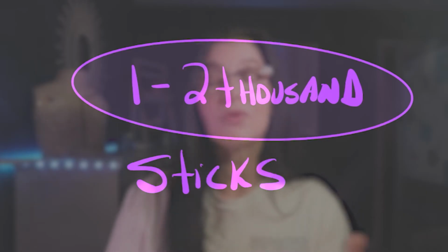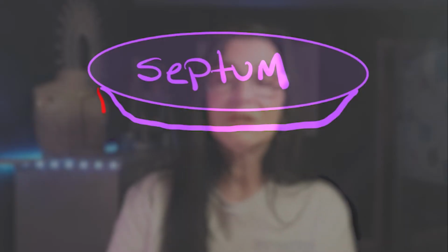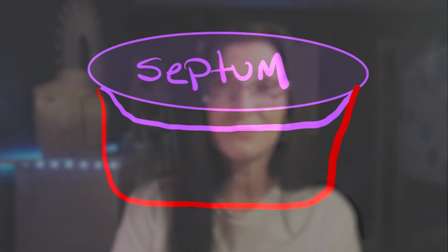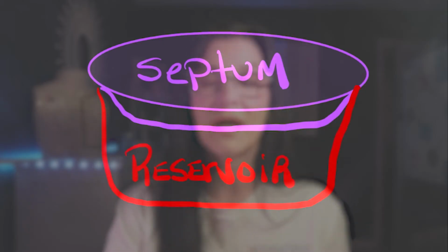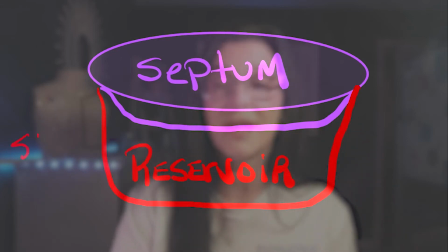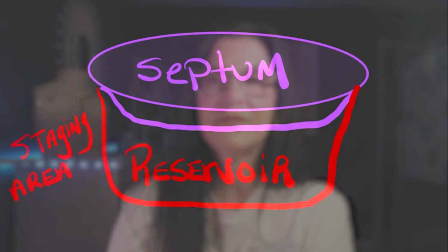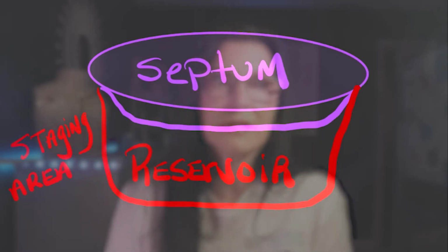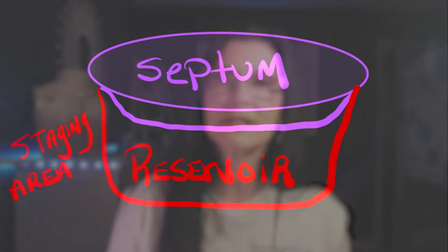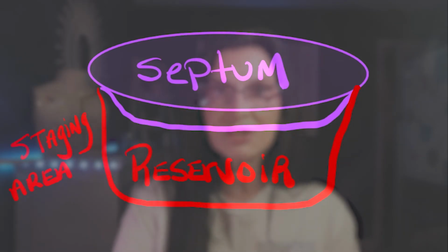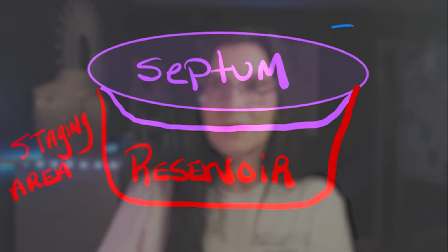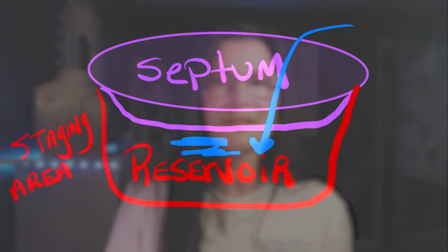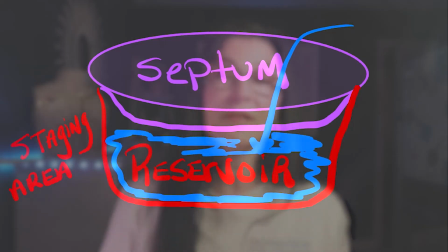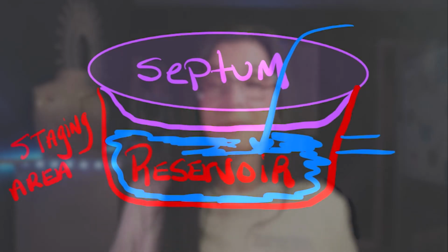On average, a silicone septum is designed to withstand anywhere from 1 to 2,000 needle sticks before it would need to be switched out. So just below the silicone septum sits the reservoir, which is a small chamber within the port body that holds the medication before it enters the catheter. And you might be asking, well, what's the point of this? Because the medication is going into the catheter anyway. It's such a small space. And you can think of the reservoir as a staging area. When the medication is delivered from the needle, it first collects here, allowing for a more consistent and controlled flow. It helps to regulate the pressure as it enters the catheter and subsequently the bloodstream.